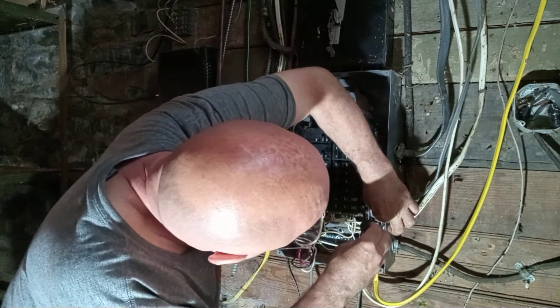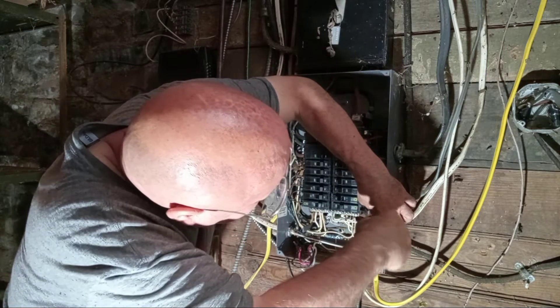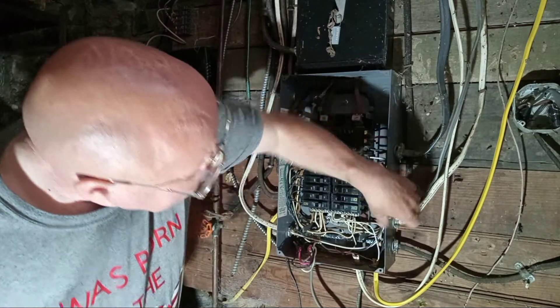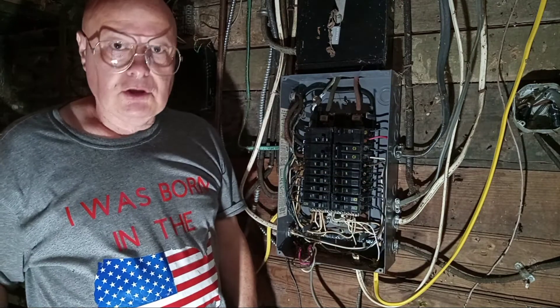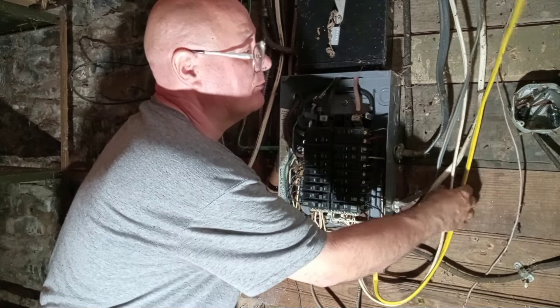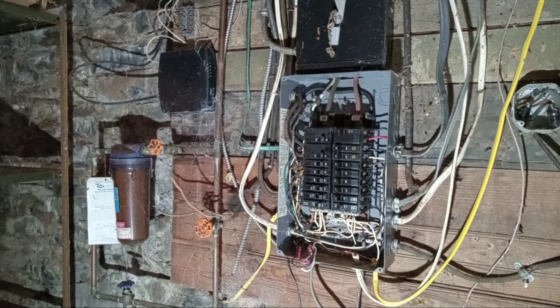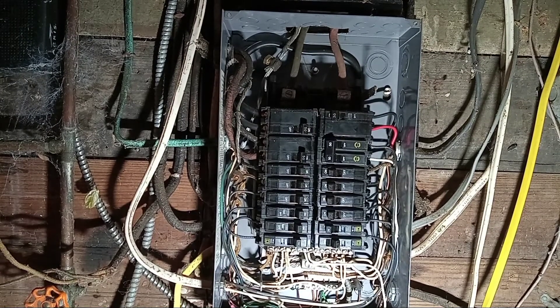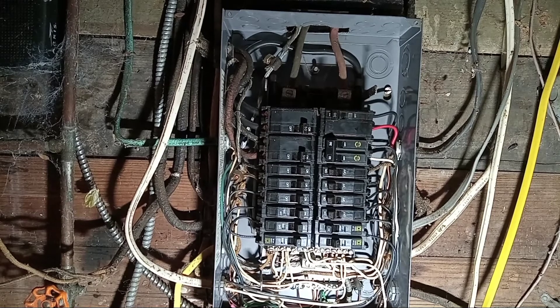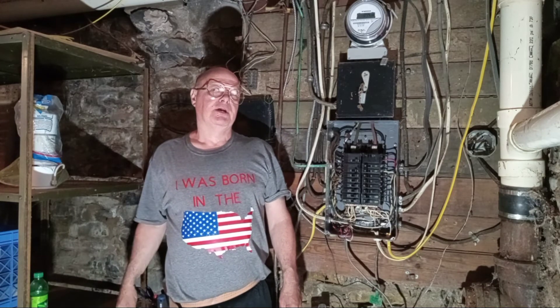Make sure it's under all the way and it's off. And that is how to install a new circuit into a breaker box. When we get some staples, we'll staple this up off camera. There's the whole entire panel box after I rewired it. So that is how to run a 120 volt line out of a Square D QO panel box. Peace. Thanks for watching.